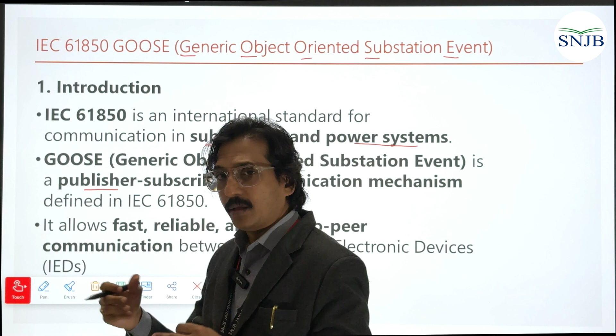This is terminology utilized in the GOOSE protocol: publisher and subscriber. It is defined in 61850. It is very fast and very reliable, and peer to peer means nodes can communicate with each other. If one circuit breaker fails, it can give information to the other breaker that this particular node has failed, and the network can continue.